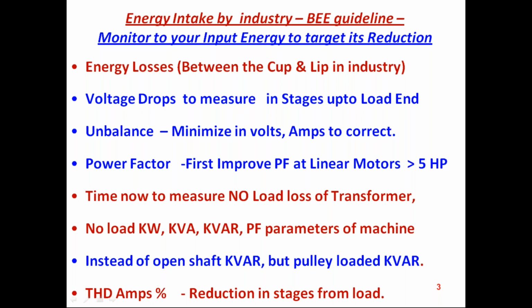And next comes the power factor, which is improved at the motor end, especially on the linear loads where the motors are operated without VFD. Then comes the no load loss in the given transformer. Some of the transformers report less than 2%, and high, say 1000 kVA and above transformers, they report almost less than 1%. In many of the industries where the transformer sizes are smaller, around 500 kVA or 250 kVA, the losses are more than 3%, 4%. This HT to LT loss is definitely to be monitored by going by the condition monitoring approach.